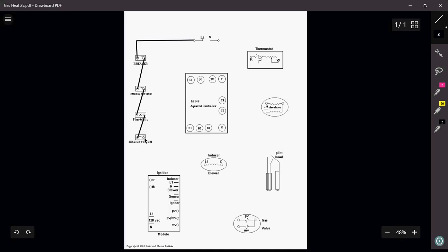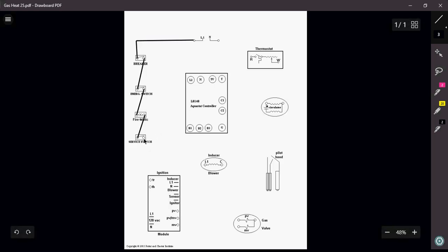I have to send power in two different directions here. I have to send power up to my Aquastat, but I also have to send 120 volts down to my ignition module because this particular ignition module needs its own power source in order for it to send out the 120 volts to power up my inducer motor.